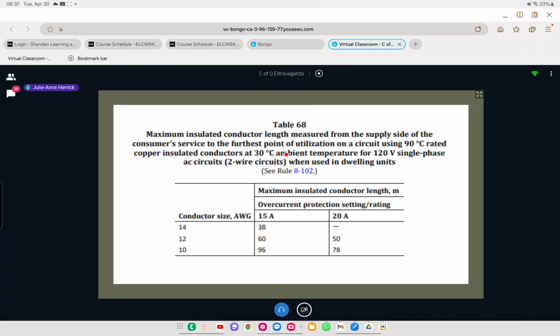So the longest you can run a 15 amp... try again. The furthest you can run a 14 gauge on a 15 amp circuit before voltage drop starts happening is 38 meters. The longest you can run a number 10 going to a 20 amp circuit before a voltage drop starts to happen is 78 meters.